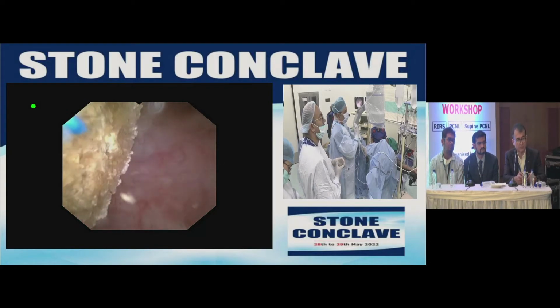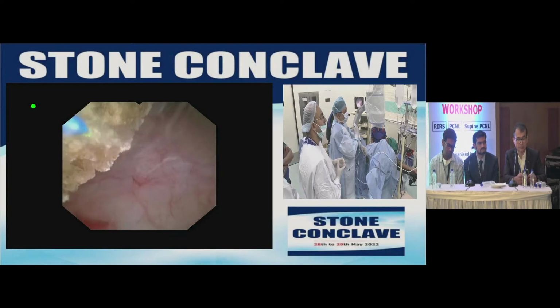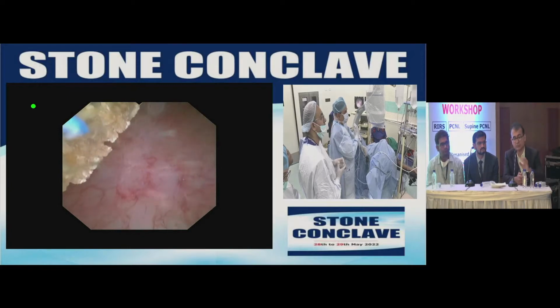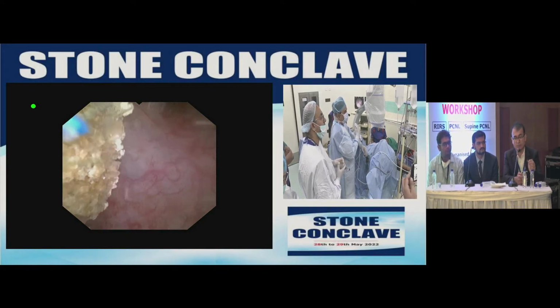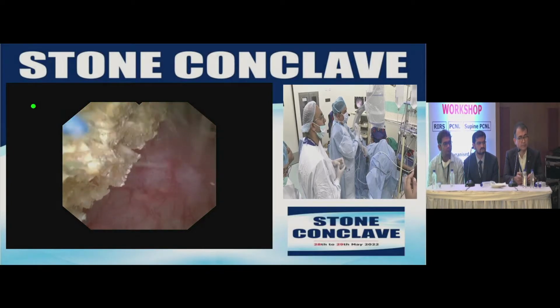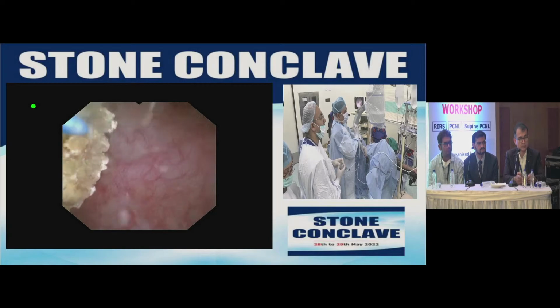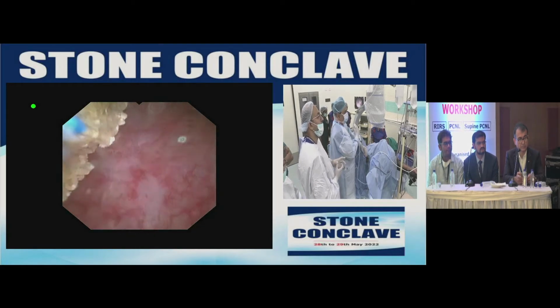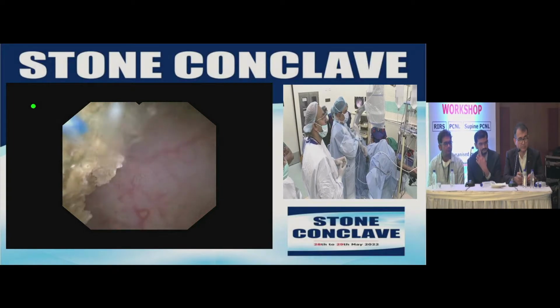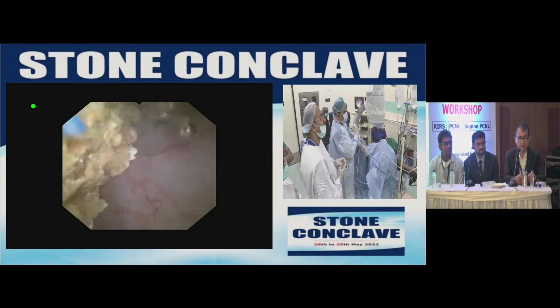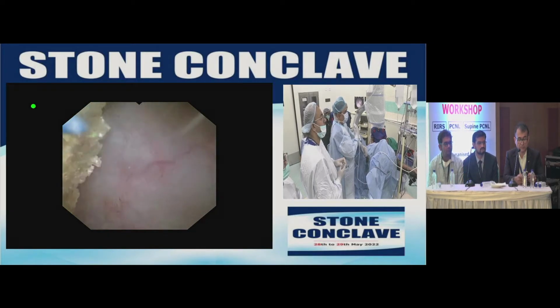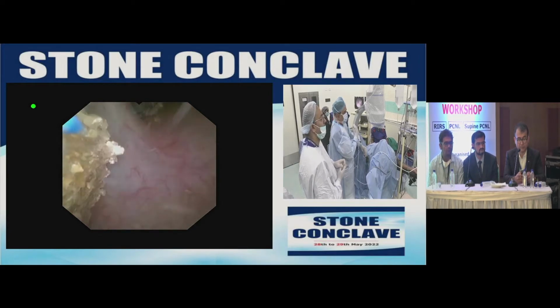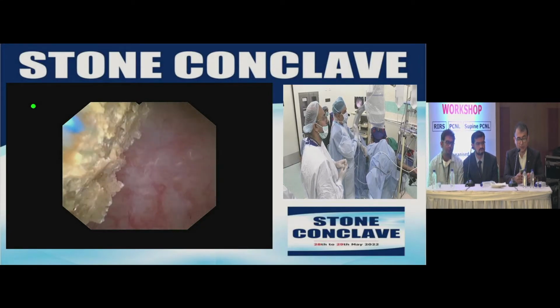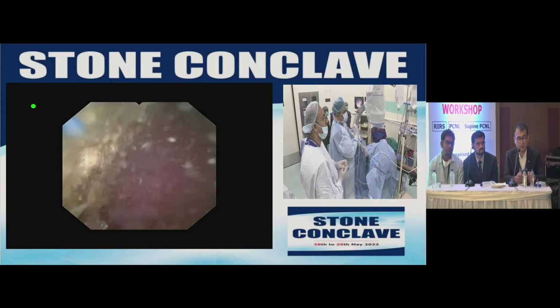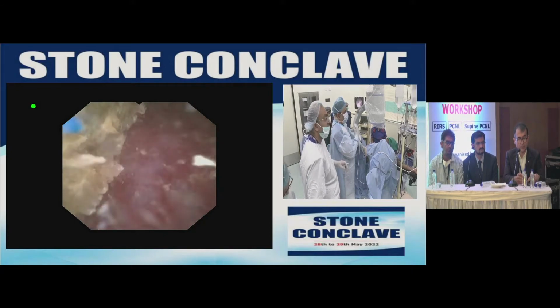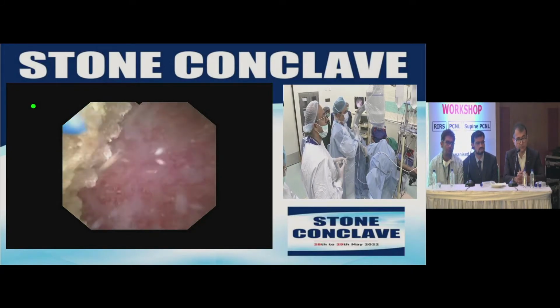Initially, I was using frequency of 100 because the advantage of thulium fiber laser is that you can increase the frequency quite high. So when I initially started with this stone management with the thulium fiber laser, I used to keep my laser frequency setting to 100 in order to speed up the procedure, and joules were 0.1 or 0.2. So the total energy was not exceeding more than 15 to 20. Maximum I go up to 20. But then I have changed my laser setting because that was producing sparks. So we are doing a study now whether the higher frequency as well as the stone composition are responsible for producing sparks as well as the carbonization.